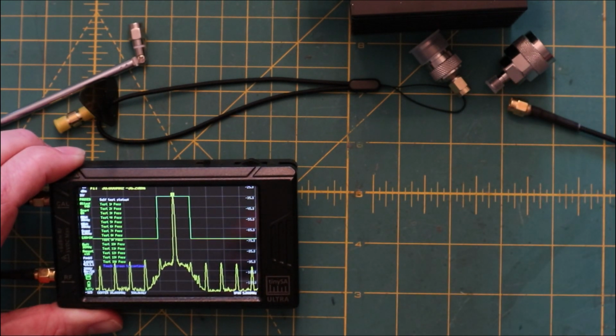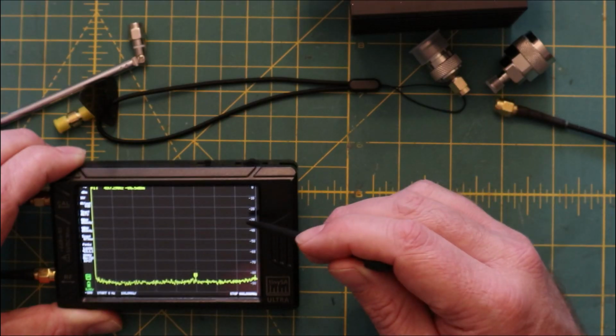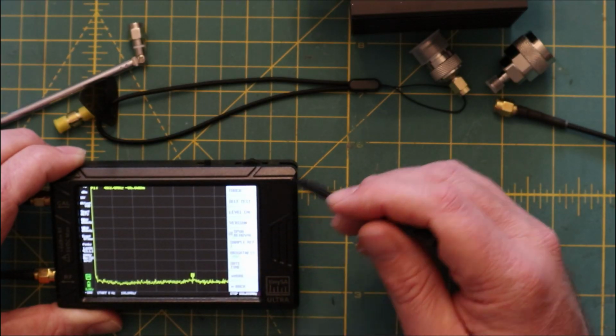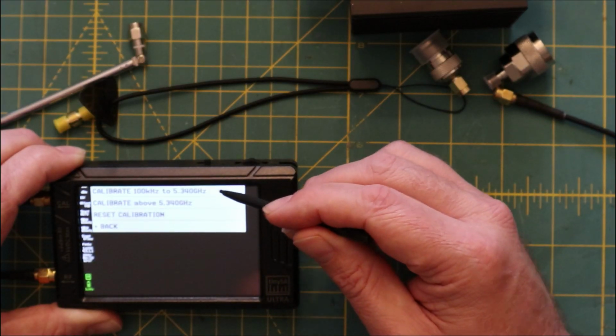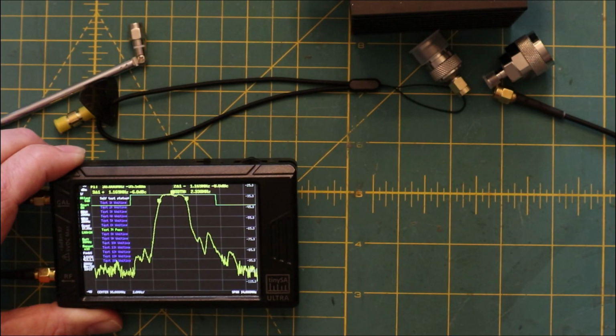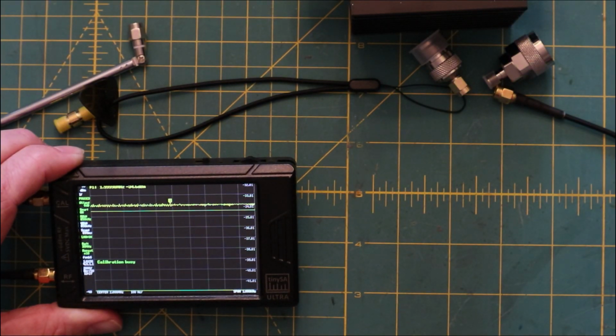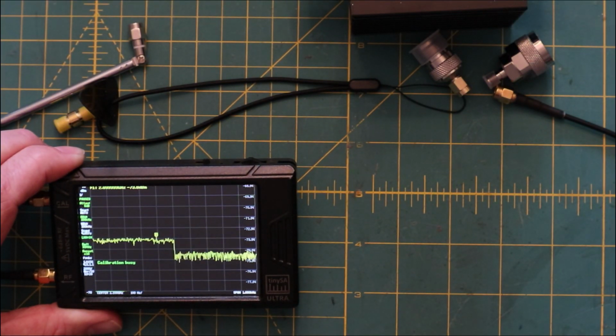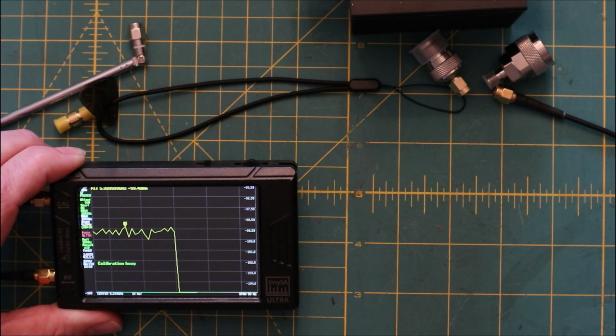Once that's done, we'll move on to calibration. We go to Config and then Level Cal, where we select the Calibrate 100 kilohertz to 5.34 gigahertz range, and let that run.